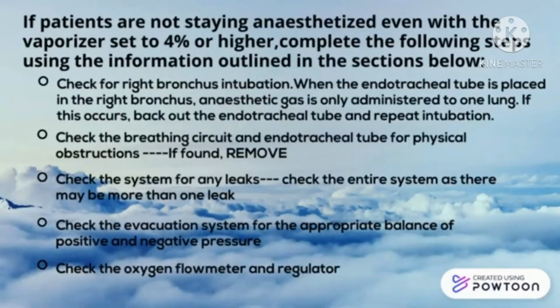Check the system for any leaks. Check the entire system as there may be more than one leak. Next, check the evacuation system for the appropriate balance of positive and negative pressure. Lastly, check the oxygen flow meter and regulator.